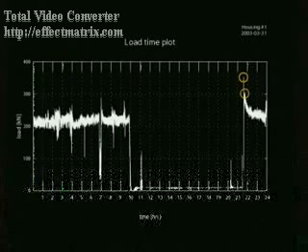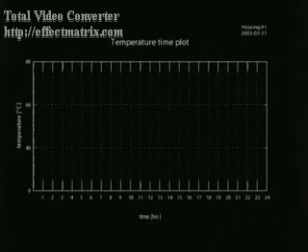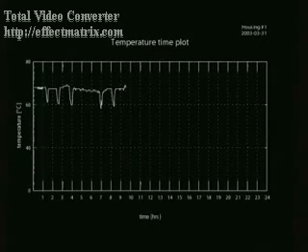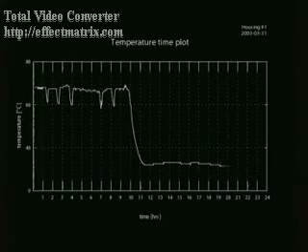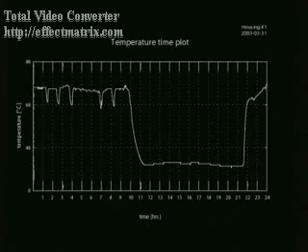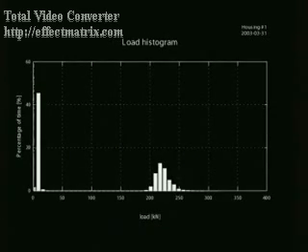A powerful tool, which shows an overview of the measured load in a specific housing, is the histogram view. The histogram gives a trained eye a quick assessment of the load situation in a roll line. When the load histogram looks nice and smooth, like in this image, everything is in order. But if the histogram should look different, there are several reasons to examine it closer. The temperature data can of course also be represented in the histogram view.